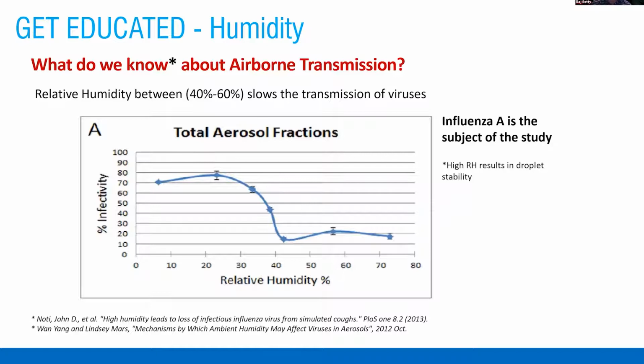So part of this is humidity. There are no good studies currently about the level of humidity and coronavirus. However, there are good studies with the influenza A virus and percent infectivity. So between 40 and 60%, there is a reduction in the percent infectivity. Now, we can't apply this universally, but building operators should have the ability to adjust their humidity levels to help mitigate the transmission. So that's where you want to start thinking as you start guiding your clients.